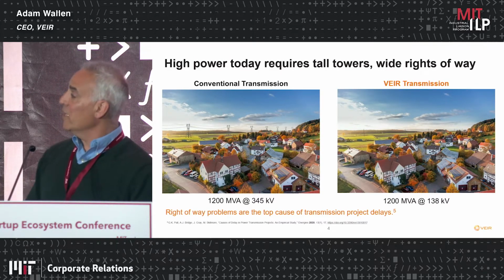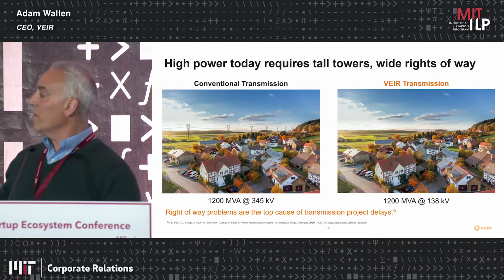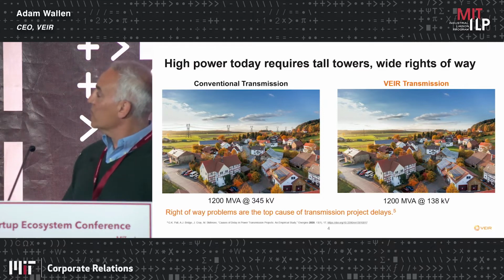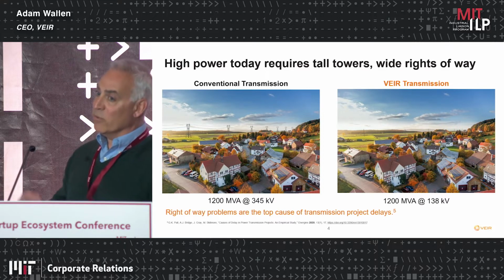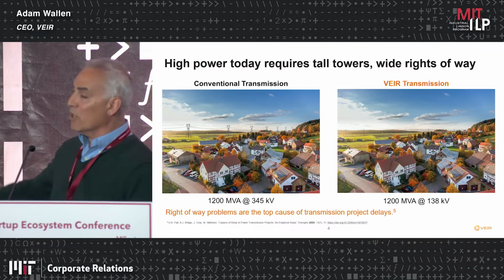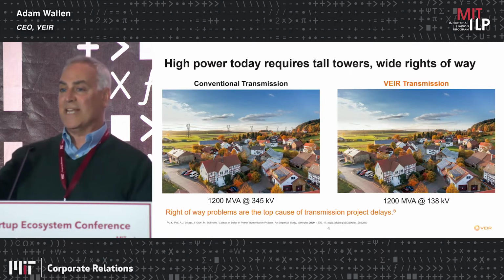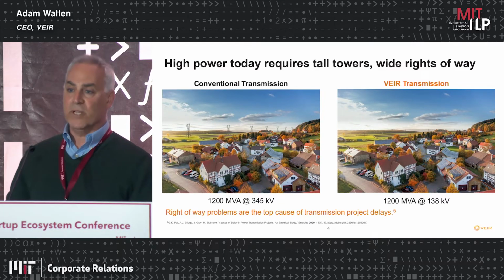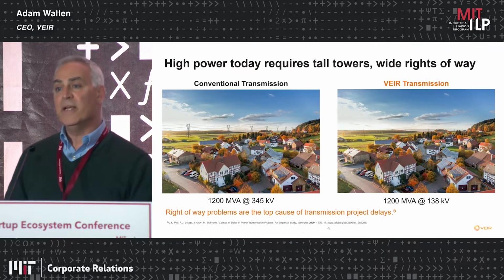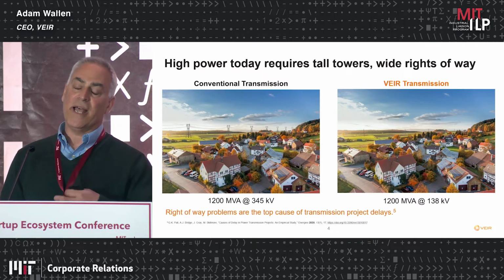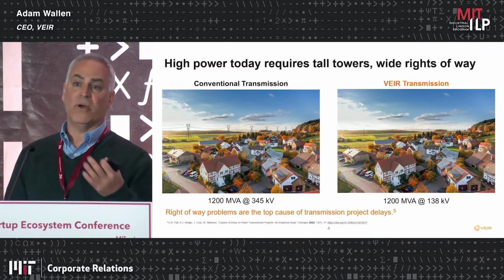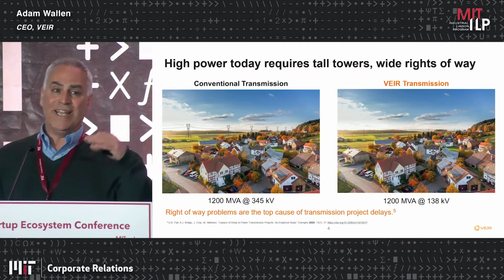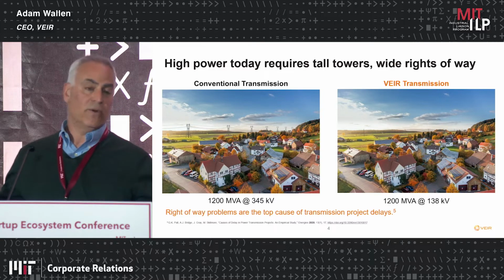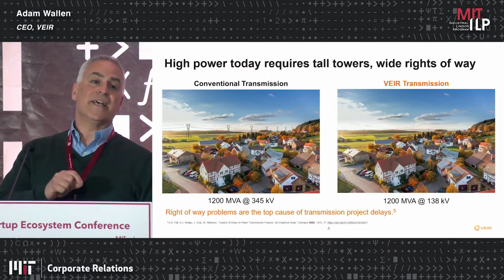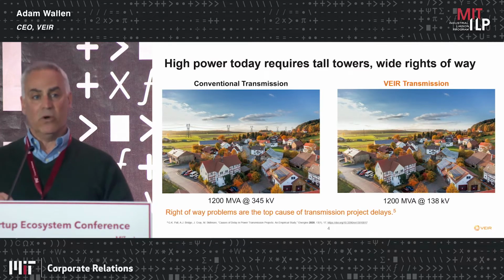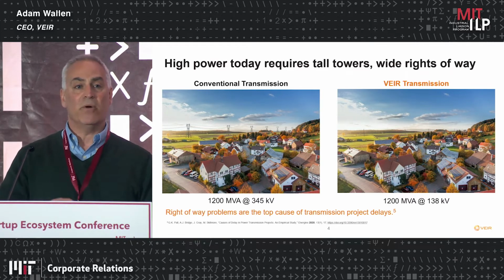This is really our vision. On the far panel you'll see a 345 kV line carrying 1200 MVA of power. On the near side panel, in the background, you'll see VEIR lines reconductored using a lower voltage, 138 kilovolts, transmitting the same amount of power through that existing right-of-way. That's the important lever we're playing: rather than re-permitting or adding new rights-of-way, which requires public review and process, and rather than increasing voltage with wider rights-of-way and higher towers to get more power through, our technology leverages high temperature superconductors with zero resistive losses, letting us put 5 times as much power through an existing right-of-way.